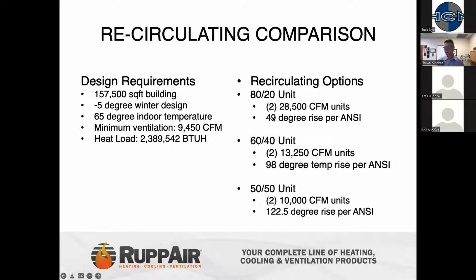We're going to talk a little in a second here also about the ANSI requirements for heating, because these are going to be limited to a lower temperature rise capability. The 60/40 style systems can utilize two 13-250 units, where the 50/50 will be the smallest units. But again, these are going to be more of a cycling on-off system. They have the highest temperature capability of the recirc style systems.